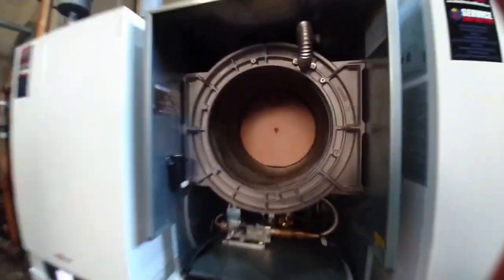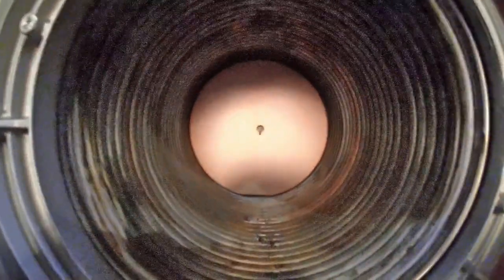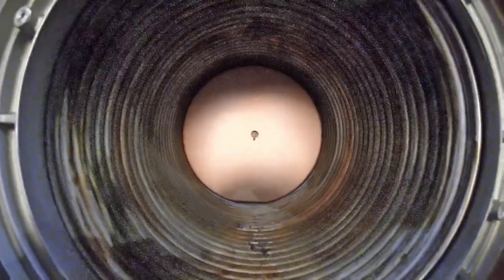Everything looks okay. We want to take a look inside the heat exchanger. We also want to make sure that the refractory at the back is good. This is not a wet back boiler, so it's important to have that there so that we don't burn through the back of the firing chamber.